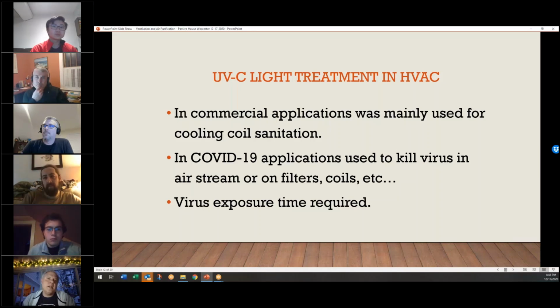The only thing I will say is you want to make sure wherever it's going in the unit that it's not exposed to things that are going to get degraded by the UVC light. Make sure the wheel is made of a material that's not going to break down, because there are certain materials, I forget, I was looking at them at one point, that'll get either super brittle or just totally break down as the light just sits there and bakes on it. It's almost like a continuous sunburn.